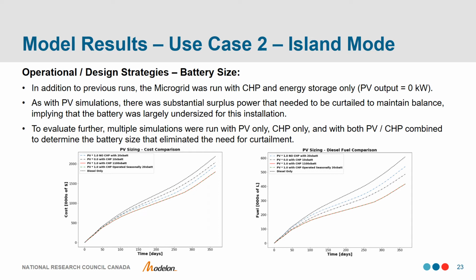With seasonal operation, however, we can operate with PV and CHP with curtailment in the summer with only a 20 times the original battery size. And you'll notice that the 1,100 times versus the seasonally curtailed simulation results with respect to cost and fuel actually produce the same benefit. So this is an important result. And note that the black dashed line at the top of each of these charts represents the original diesel-only configuration. So we're seeing some significant benefits.